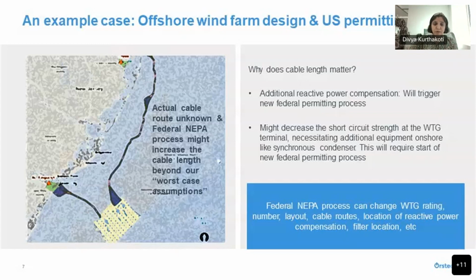When we exceed some limits, we need reactive power compensation, and once we add that, the impact to the grid might be very different. Given that the cable route has increased significantly, there are engineering challenges—it might also decrease the short circuit strength at the turbine terminals out in the ocean. In some projects, we had to bring synchronous condensers back in.